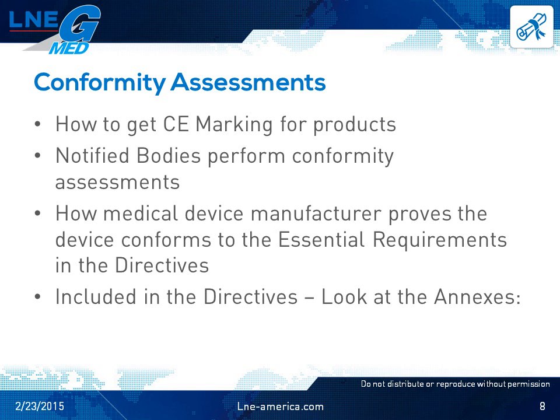Performing a conformity assessment is the method that manufacturers have to use to have the ability to put the CE marking on their products. By going through the conformity assessment, the medical device manufacturer proves that his device conforms to the essential requirements in the directives. For devices whose conformity assessments require a notified body, the notified body performs the conformity assessments.